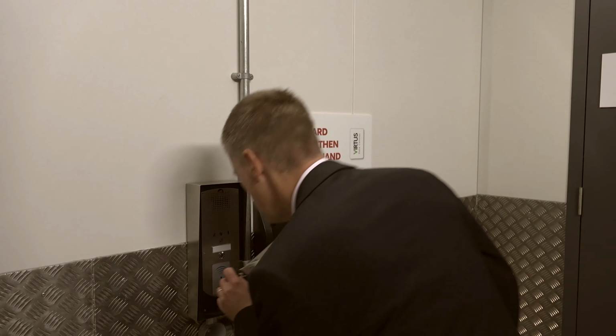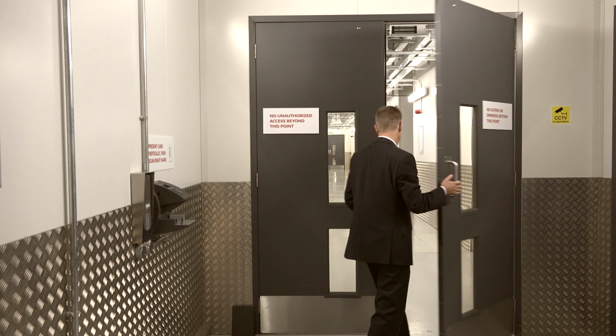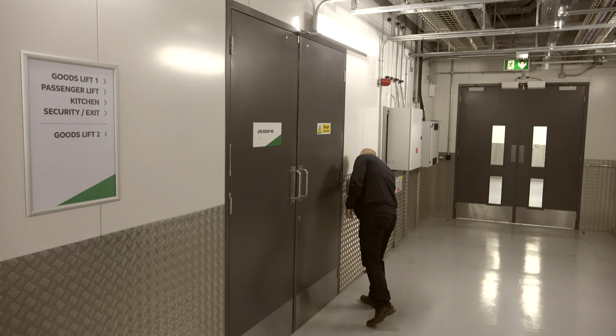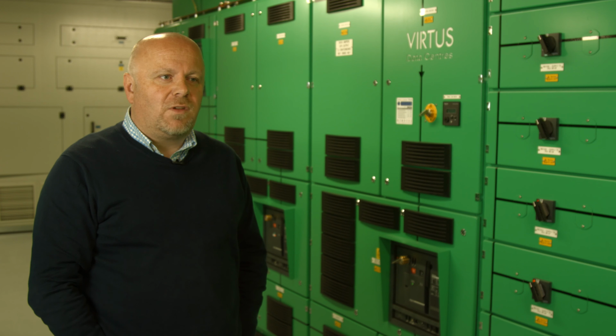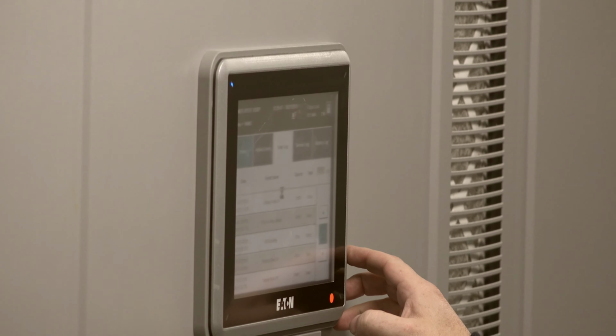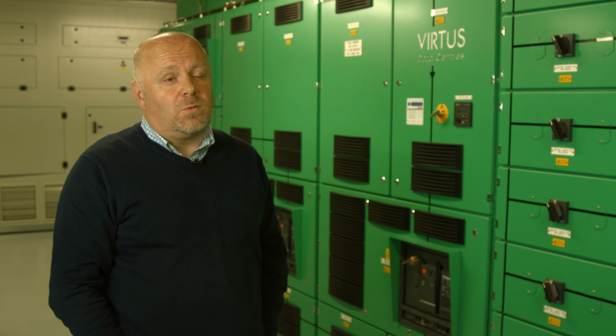The flexible nature of the data halls at London2 allows ultra-high densities to be deployed. The hot aisle containment arrangement and the 2 kilowatts per metre squared load density can handle almost anything you throw at it. There was a lot of work involved, assisted by the consultant team. We spent a lot of time and money making sure that what we were buying was the right equipment. What's come back now is a change from traditional DCs in the way we cool the rooms, but it's far more effective and it gives us greater flexibility within the data hall. We've proved by computer modelling that we can cope with most size racks in a data hall, whereas a chilled water system would be restricted.